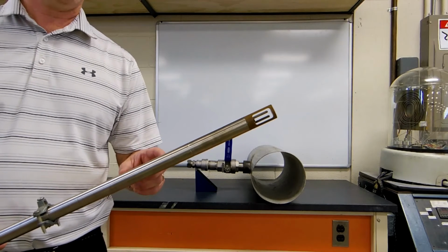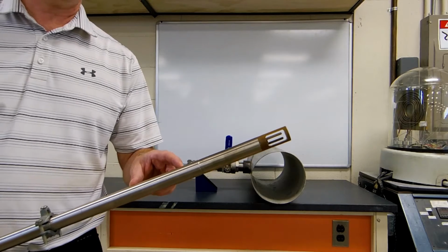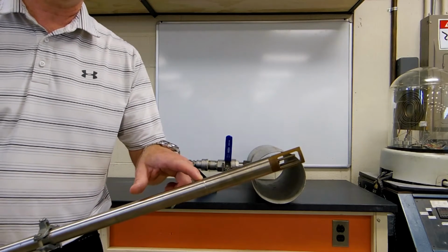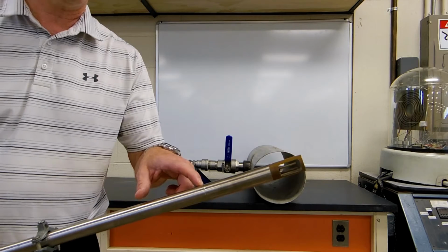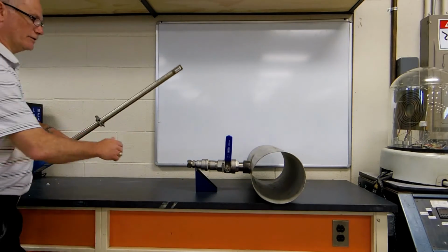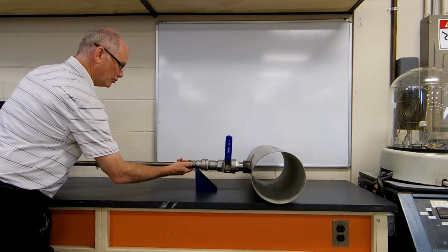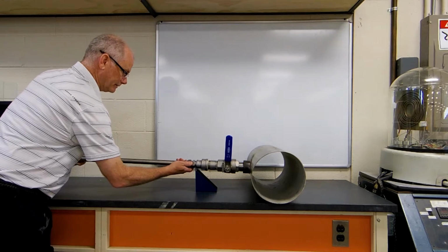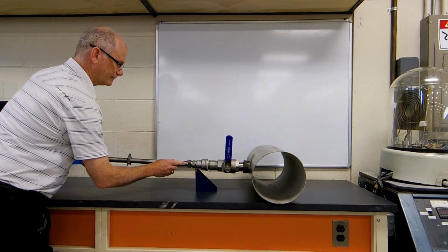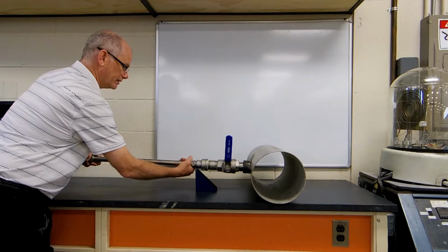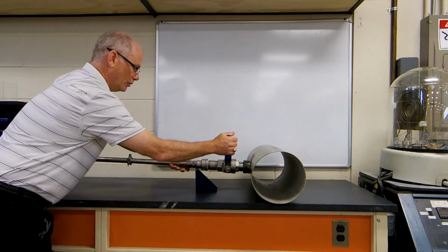The probe can be inserted into the vent line while the vent line is under vacuum by utilizing the extraction mark on the RheoVac probe. With the valve closed, insert the probe to the extraction port. Secure the compression fitting and open the valve.